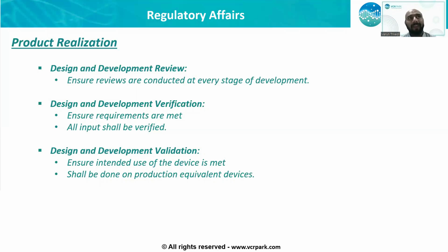Design and development verification and validation are two very important things. Verification focuses on meeting the requirements and it needs to be conducted at every stage in the development activity. Can be in iterations, can be done multiple times in the overall development activities. Validation, on the other hand, is something that we do to ensure that the intended use of the device is being met. These are two very different activities because one is in sync with the requirements of the device, the other is in sync with the intended use of the device.